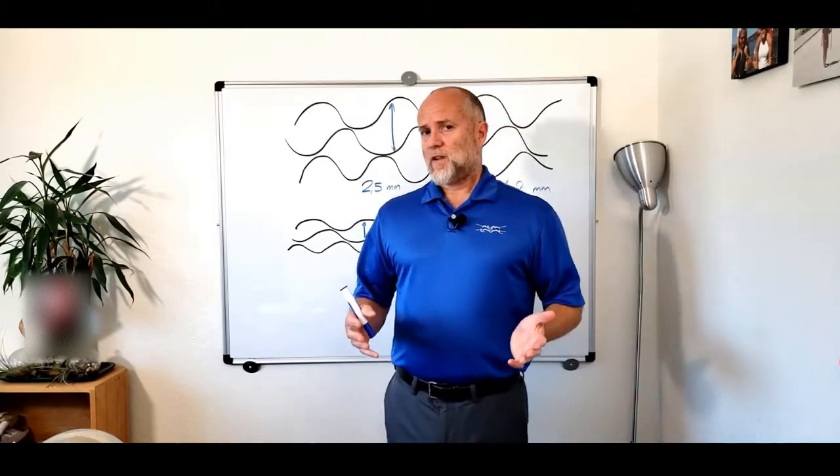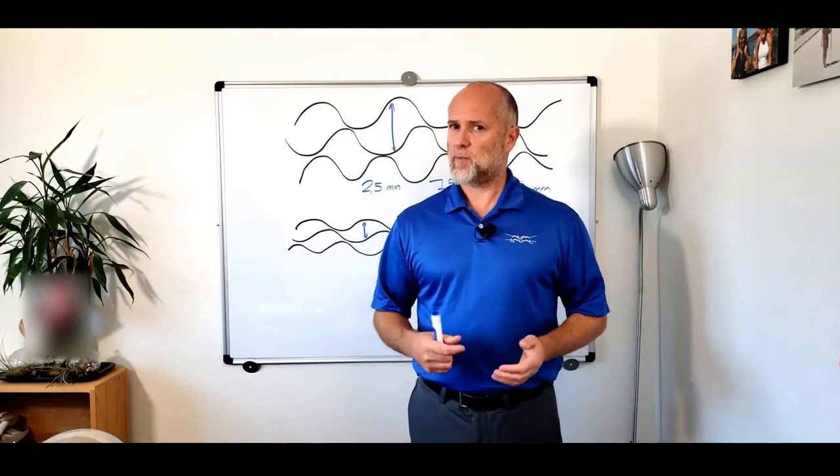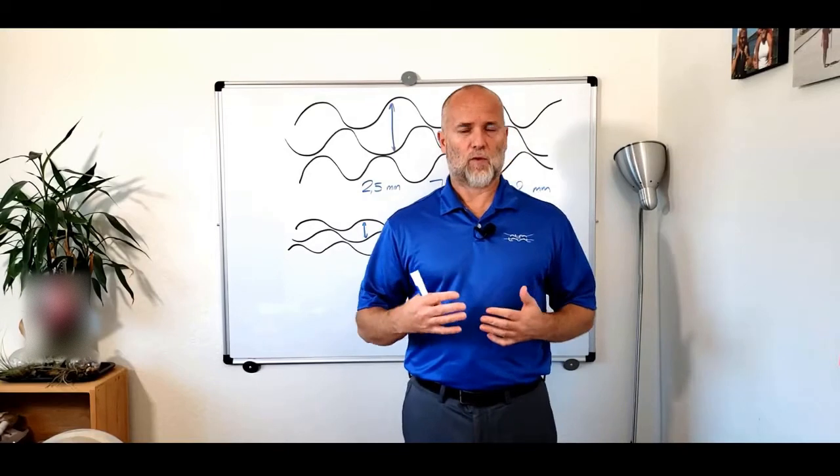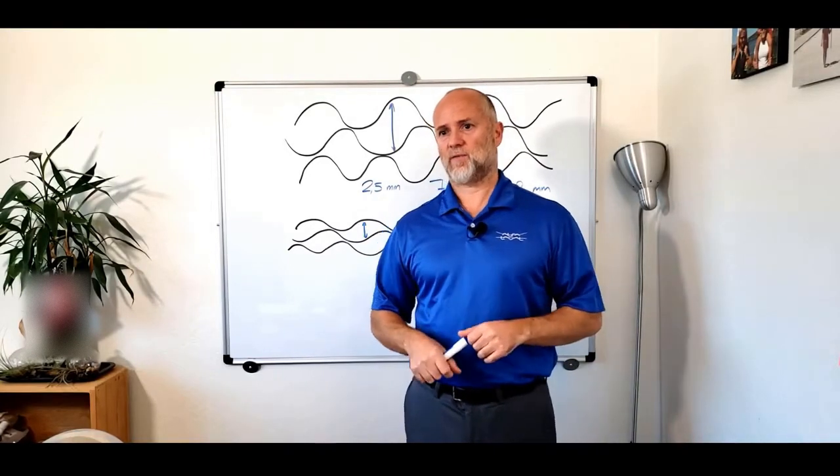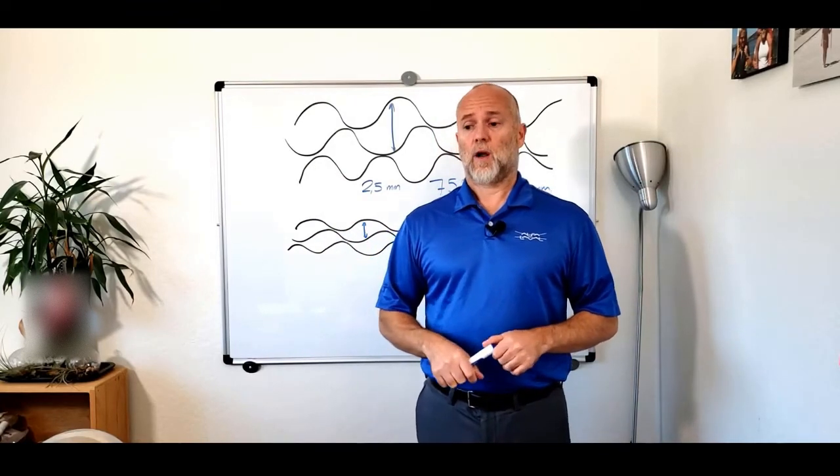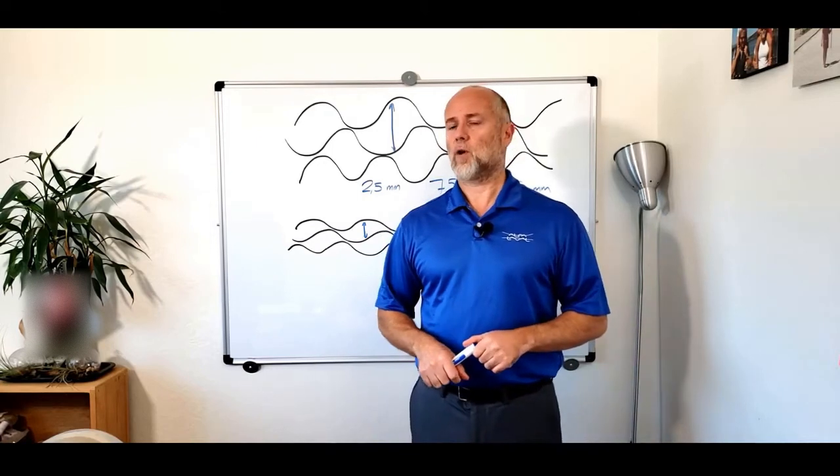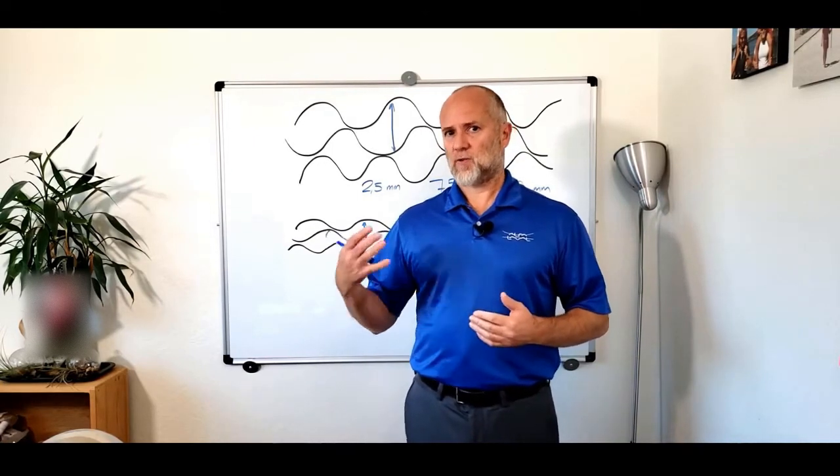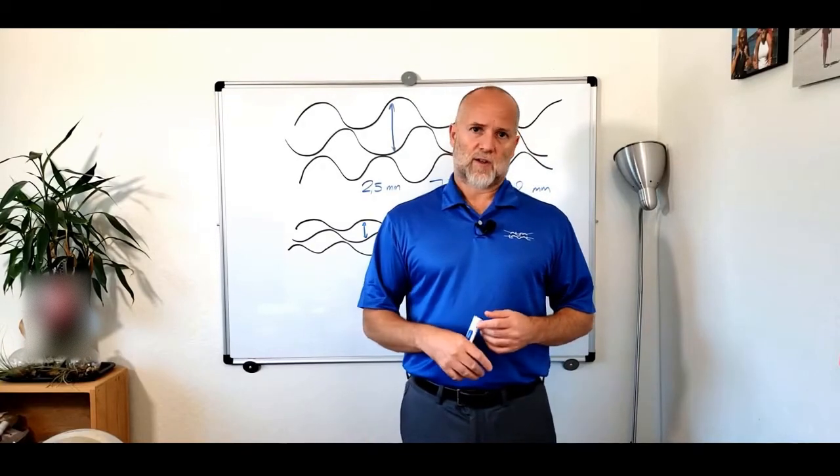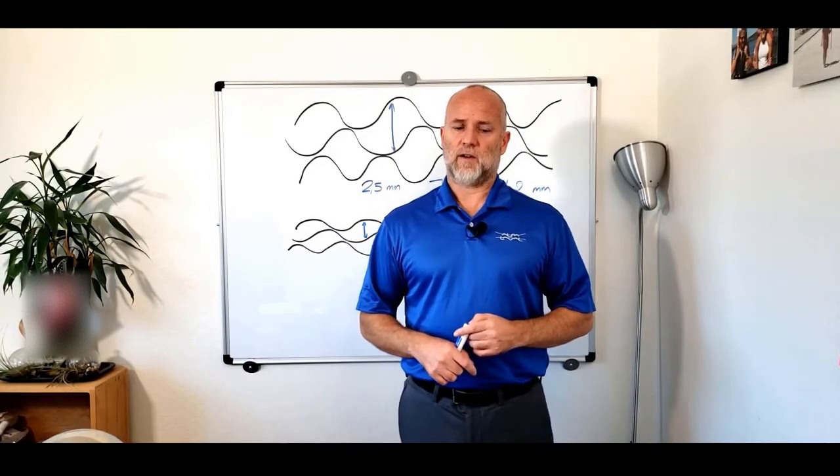With this kind of filters, you screen out fairly large particles. They are not particularly helpful for another kind of fouling which is very fine particles, dust, sand, seeds from the cooling tower, or scaling from the water quality. At that point the shear stress inside of the heat exchanger is more important, but we have discussed this concept at length in previous videos.